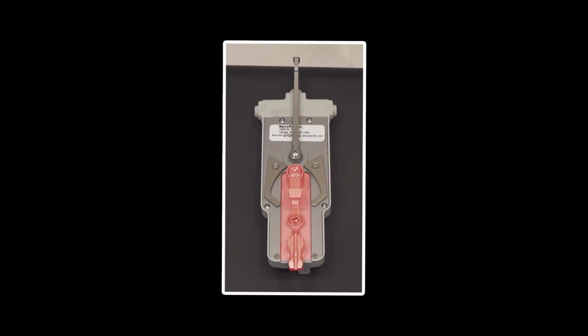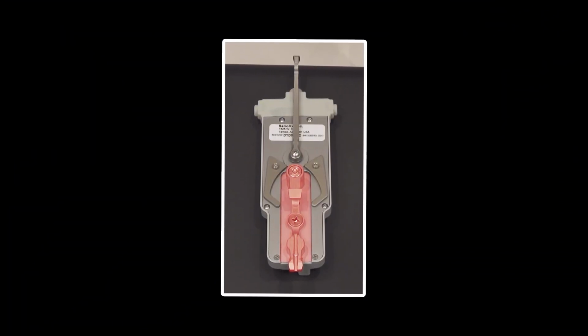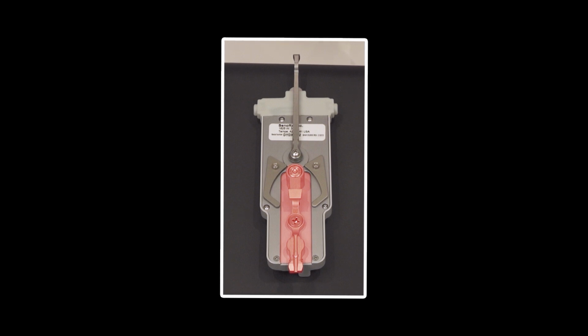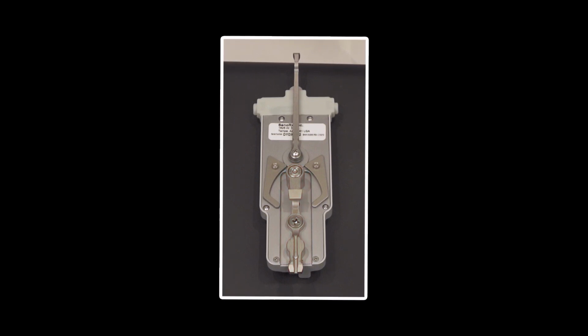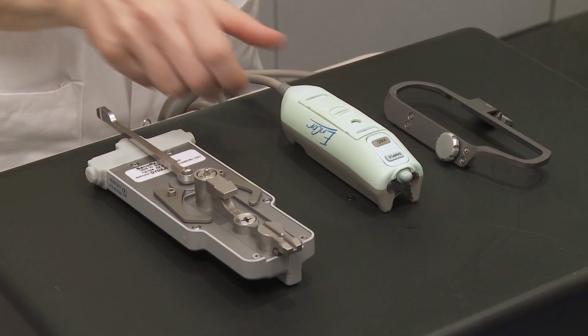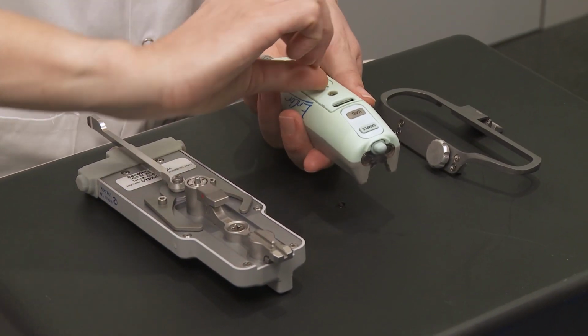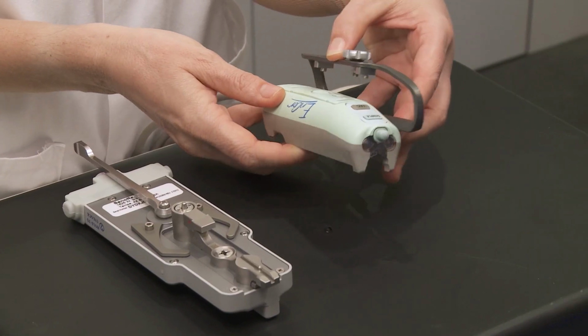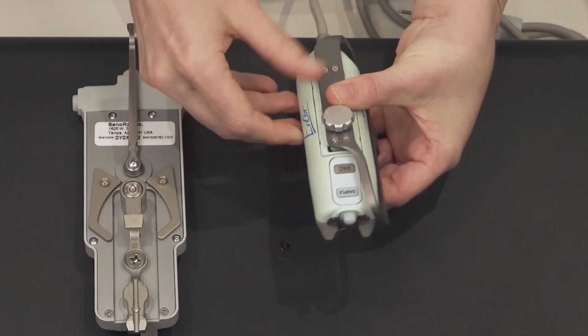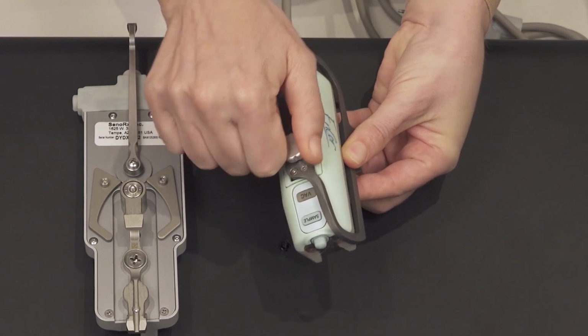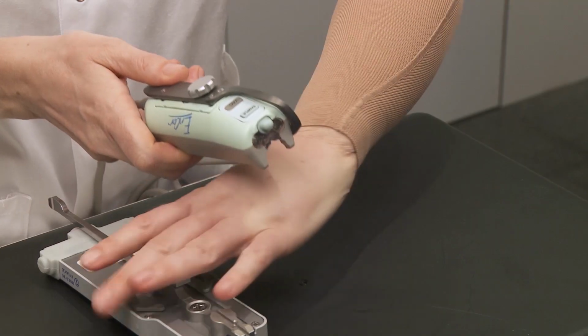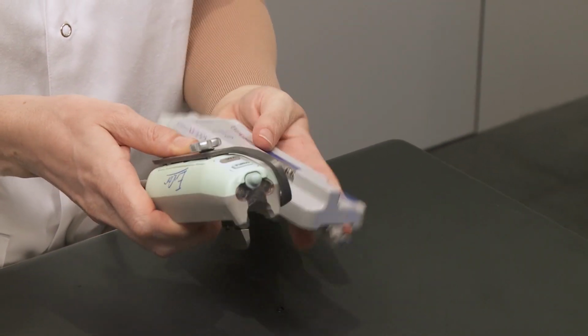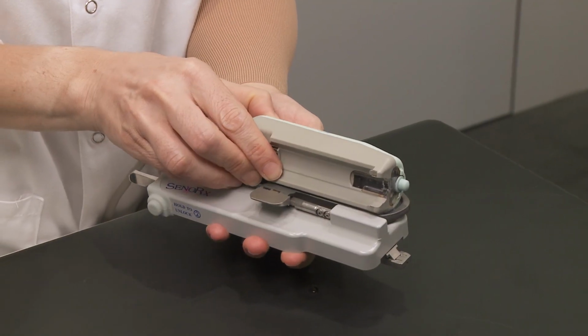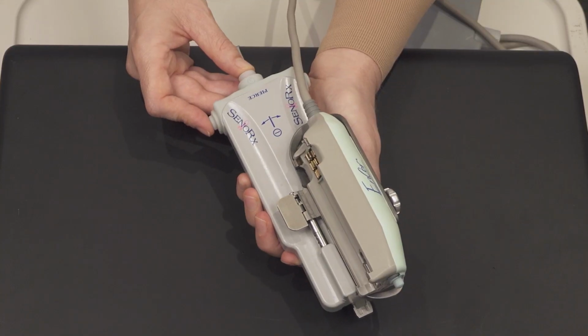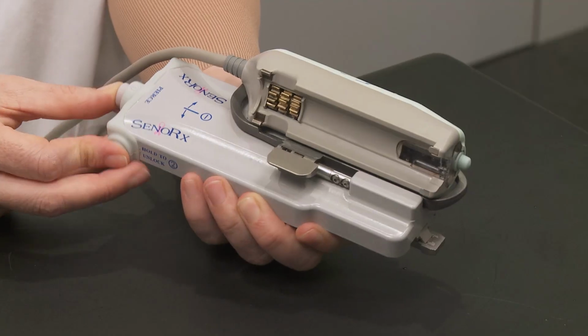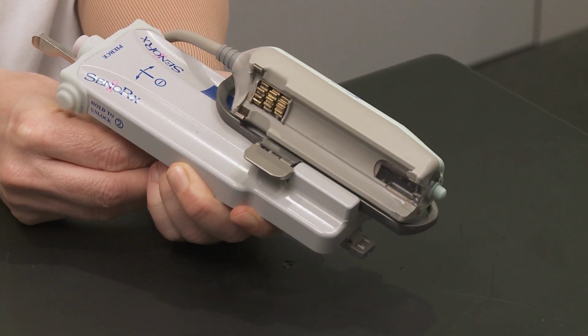As shown, the dedicated Amulet Innovality adapter for EnCor, E adapter, is already attached to the fire forward piece. Attach the EnCor bracket to the driver and adjust it. Attach the driver to the fire forward piece. For needle calibration accuracy check, ensure post-fire position is set.